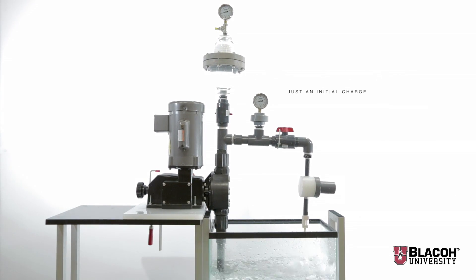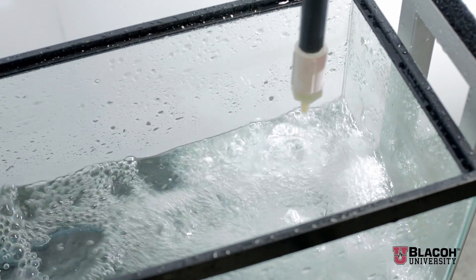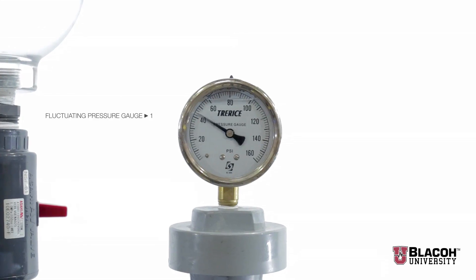This metering pump is a single diaphragm pump. Being a single diaphragm pump, it creates a start and stop action with each stroke of the pump. That start and stop action can be observed in the system pressure gauge which is fluctuating between 10 and 50 psi.